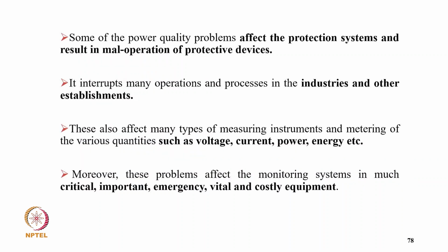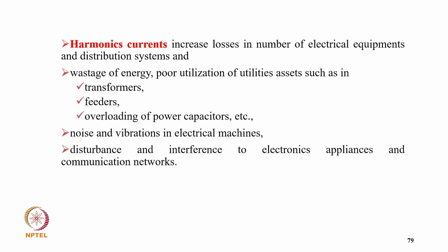Some power quality problems affect the protection systems and result in mal-operation of protective devices, interrupting many operations and processes in industry and other establishments. They also affect many types of measuring instruments and metering of various quantities such as voltage, current, power, and energy. Moreover, these problems affect the monitoring systems in much critical, important, emergency, vital and costly equipment. Harmonic current increases losses in a number of electrical equipment and distribution systems, wastes energy, and causes poor utilization of utility assets such as transformers and feeders, overloading of power capacitors, noise and vibration in electrical machines, and disturbance and interference to electronic appliances and communication networks.